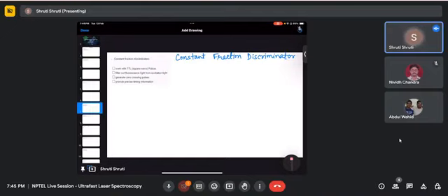But ma'am, how much power do you put into the sample? Laser power, diode laser power. It will be a pulsed laser. The power can be decided based on the fact that we need only 1 to 2% of the photons, the emitted photons. So we adjust the power accordingly. The software shows whether you are within 2% or more than 2%. If you are more, then you decrease the power. And what is that value?